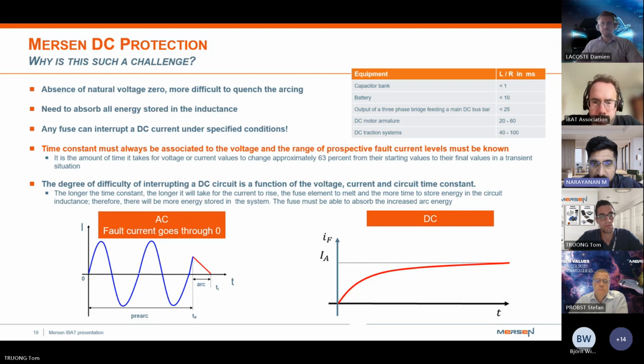The absence of a natural zero affects the rate of rise of current, the di/dt, shown on the right-hand side. This is predominantly dependent on the inductance in the circuit. Depending on the application - a capacitor bank, a battery application, or a DC traction system - the inductance to resistance ratio present in the circuit is the key factor for DC fault mitigation.